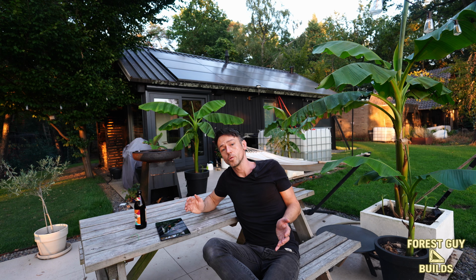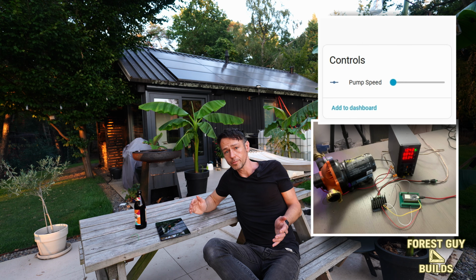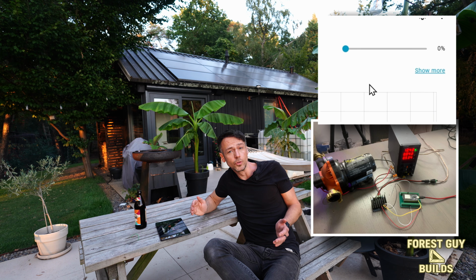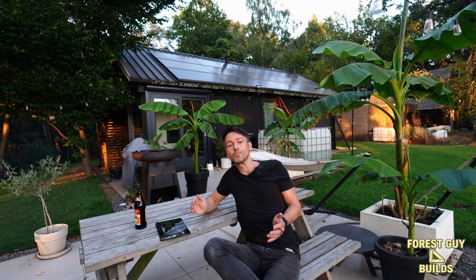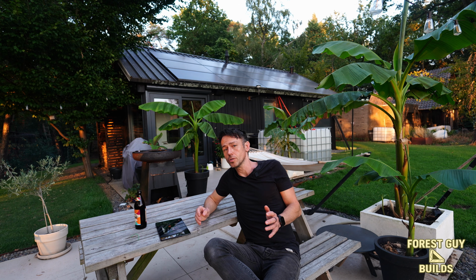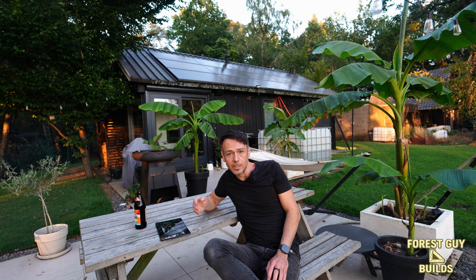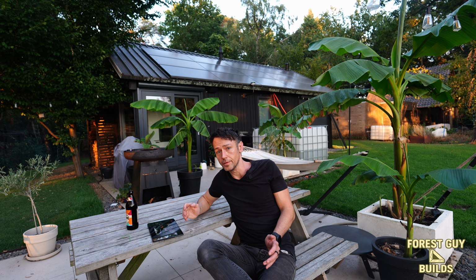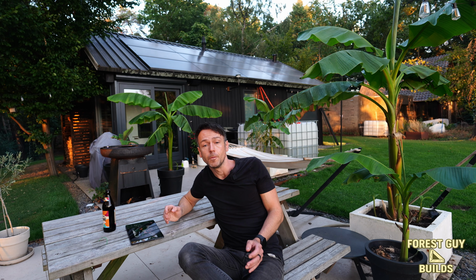So to quickly summarize what we've done: for me, the biggest improvement is the PWM controller. I now have direct control over the groundwater flow, which affects both the amount of water I use and the cooling capacity of the system. That becomes even more important as we get close to condensation on the floor. If I detect we're cooling too much, I now have a tool that allows the system to simply reduce the flow. There are several ways I could eventually detect and control that, but I'll keep that high level for now.